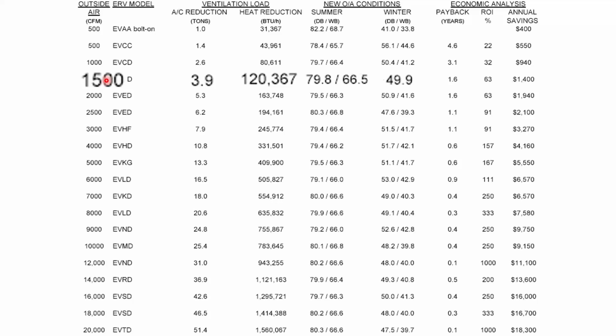And this was based on a negative 10-degree day. So this guy's going to get 50 degrees coming off the heat exchanger on the outside air. It's going to heat it up 60 degrees. This payback was pretty good, 1.5 years. If you look up here, small stuff, 500 CFM, the paybacks start getting pretty bad, 4 or 5 years. If you look at a residential ERV, which is typically 100 to 200 CFM, the paybacks are typically double digits in years because you have a lot of technology, but you don't have a lot of airflow to recover energy from. So it's kind of hard. I'm not saying you shouldn't put an ERV in residentially. I'm just saying don't do it for the financial reasons. Do it because of altruistic reasons. You know, you want to be good kind of thing.